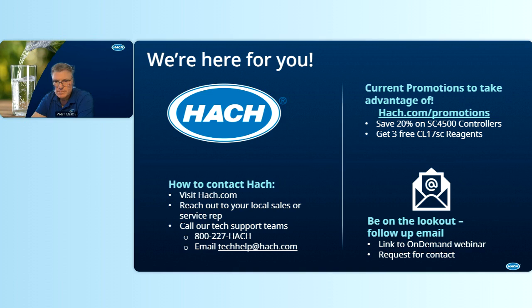All right, thank you. Next question is, how well does the amperometric unit work on chlorinated well water that has not gone through a normal potable water filtration plant, with variable well water composition as the well cycles on and off? That depends. It's one of the tough applications. I envision what you're talking about. So first of all, if you look at that selection guide, the last slide was on can your utility provide uninterrupted flow? Because interrupted flow will affect performance of amperometric.